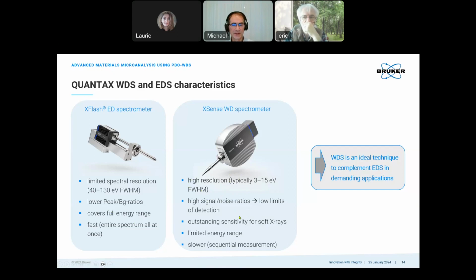It shows higher signal-to-noise ratios, so 10 times higher, which also means 10 times lower limits of detection, so very good for trace elements. And a third point, which is special for a system like ours with the Grazing Incidence Optic, is the outstanding sensitivity for the low energy X-rays, which means we can nicely determine light elements, but we can also nicely apply it to low kV applications. Which allows us to operate with not only spectral resolution, but very high spatial resolution. And Eric will give some examples on such applications with high spatial resolution.